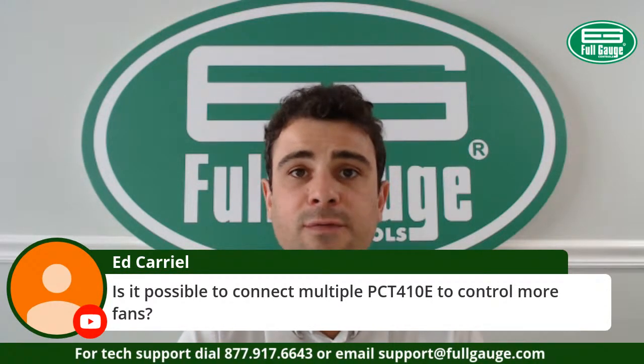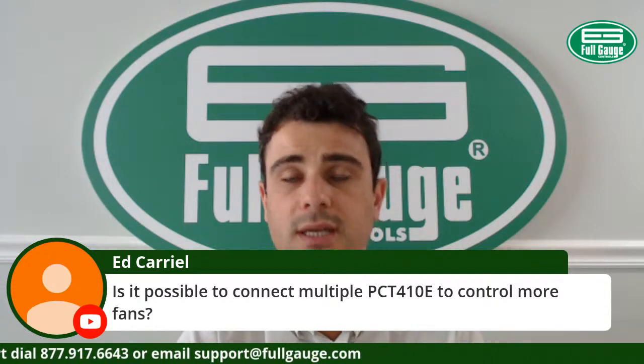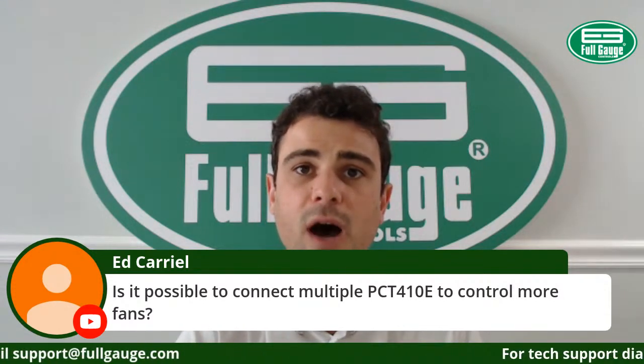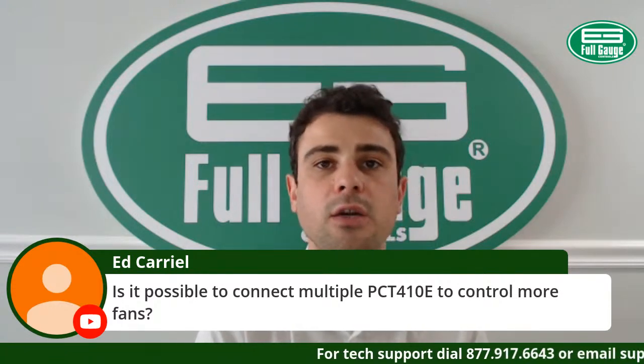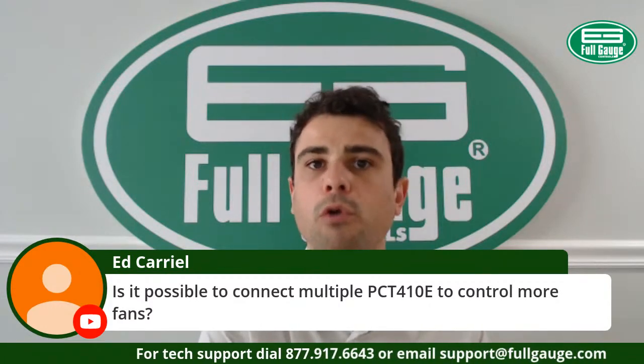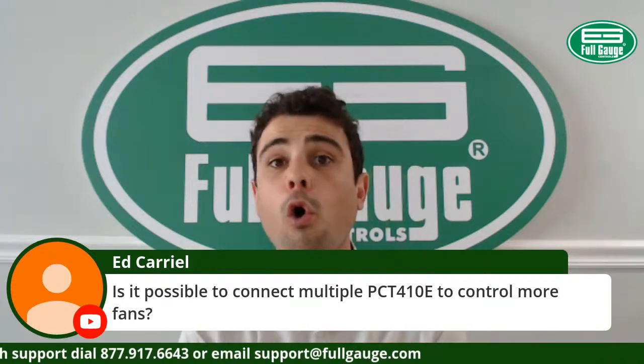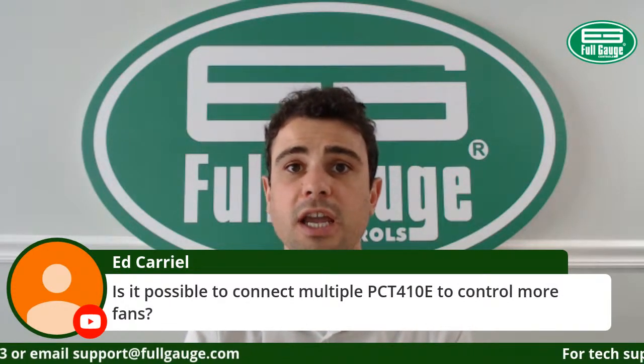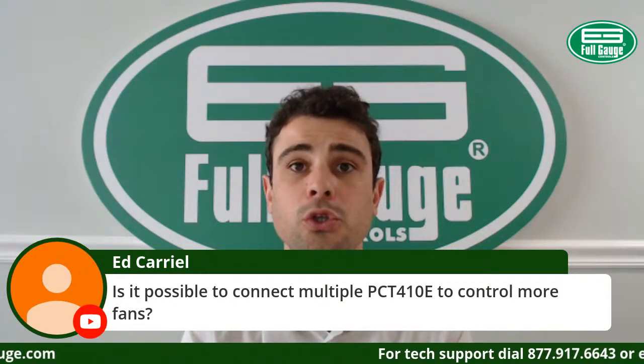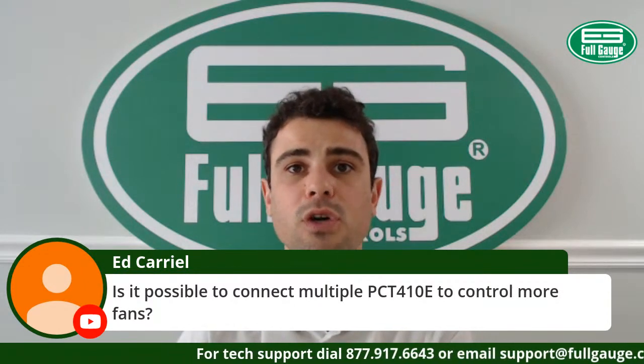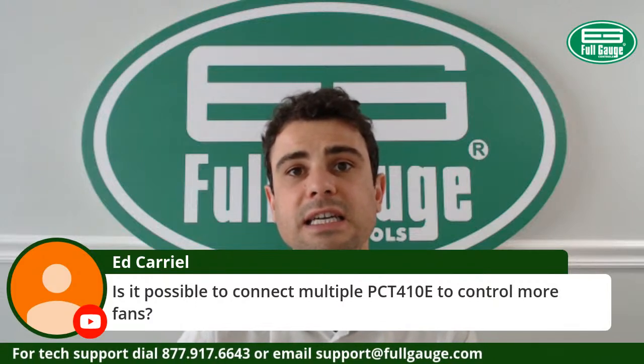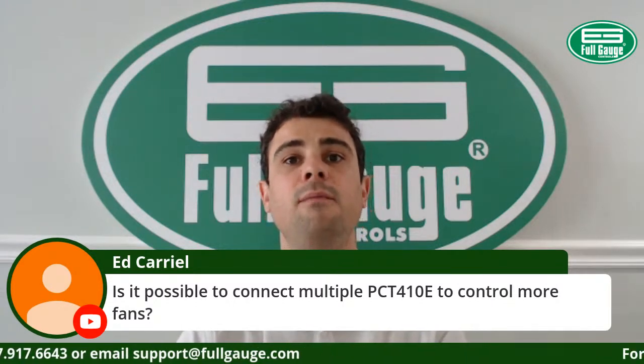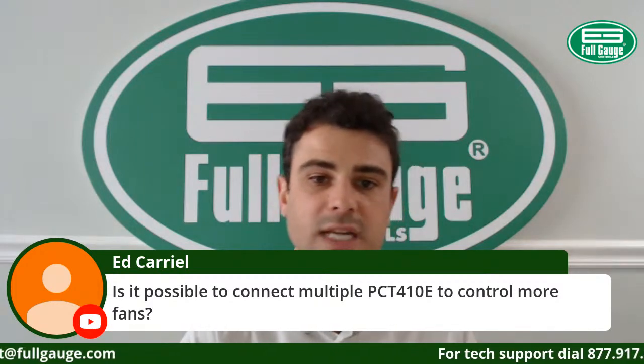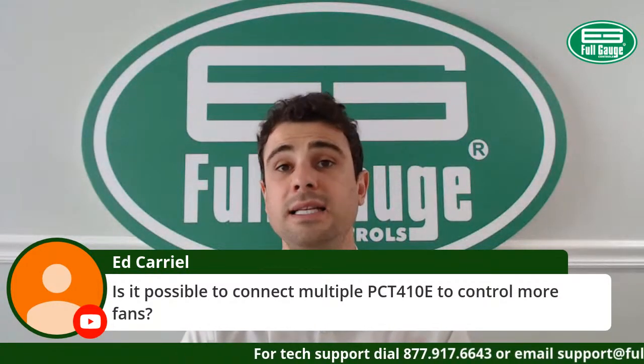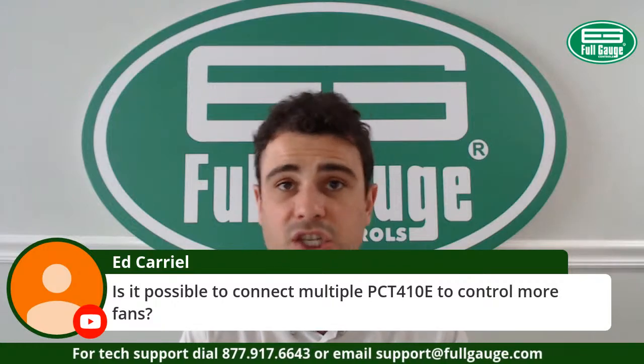The PCT410E provides 2 RS485 communication ports. One of the RS485 ports is used to communicate with the Sitrad software for remote monitoring and control. The other RS485 communication port is used to connect another PCT410. So you can connect PCT410s in series to control more condenser fans, or let's say you want to control suction and discharge.